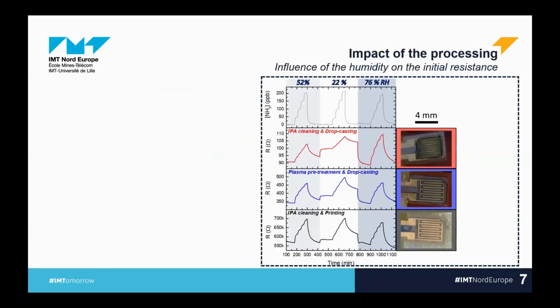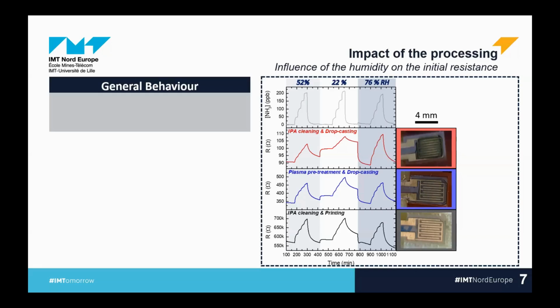So basically, what we do is inject little by little an increase of ammonia between 0 and 200 ppb, at different humidity levels: 52%, 22%, and 76%. Here you can see that independently of the processing, we observe the same trend where the resistance increases with ammonia concentration. We have a good sensor, they are working.